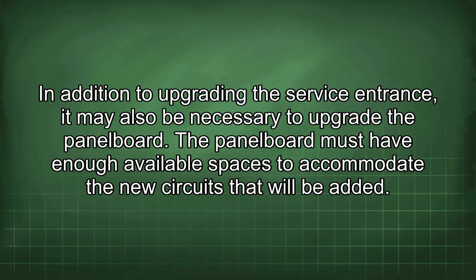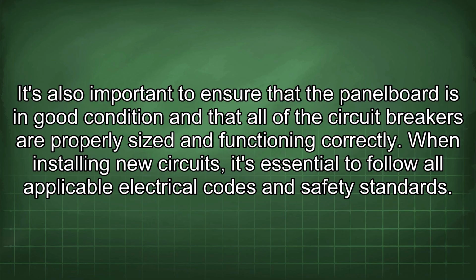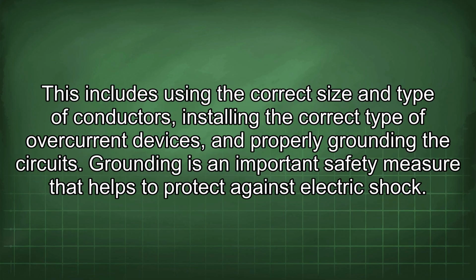The panel board must have enough available spaces to accommodate the new circuits that will be added. It's also important to ensure that the panel board is in good condition and that all of the circuit breakers are properly sized and functioning correctly. When installing new circuits, it's essential to follow all applicable electrical codes and safety standards. This includes using the correct size and type of conductors, installing the correct type of overcurrent devices, and properly grounding the circuits. Grounding is an important safety measure that helps to protect against electric shock.